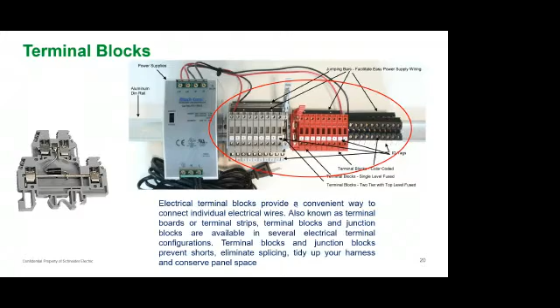So you can use it for different applications distribution into a single panel. And the SMPS selection should be based on the number of loads current available. So you will be having so many devices available in a panel, which doesn't mean that a single SMPS can be used to distribute everything. There is a current calculation ratio which you should use to select number of SMPS you require inside a panel. And these terminal blocks will be having a Zener diode inside, which is also used to protect these terminal blocks. When something goes off, the Zener diode burns. There is also a fuse cartridge option available in these terminal blocks. If the current rating is exceeding the rated value, the fuse blows and it protects the rest of circuit. That's how these terminal blocks work.